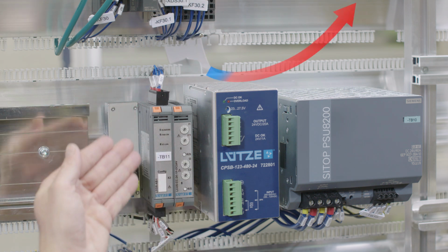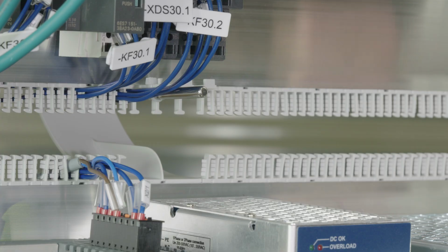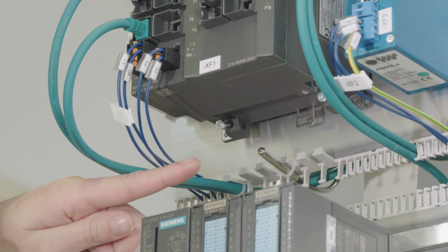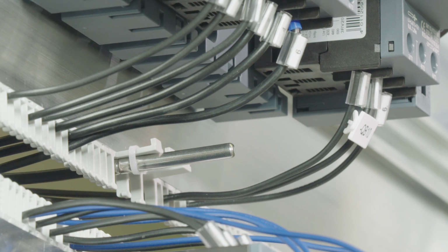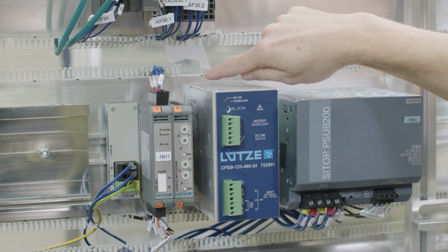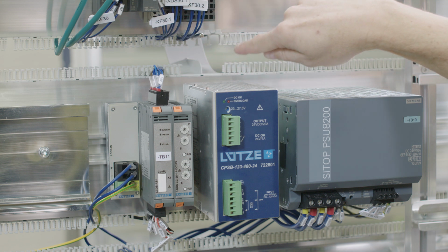The control unit also includes 3 PT100 sensors, which switch the air blower on or off when the interior of the cabinet is above the required temperature. The temperature sensors are placed underneath sensitive components where hotspots could arise.